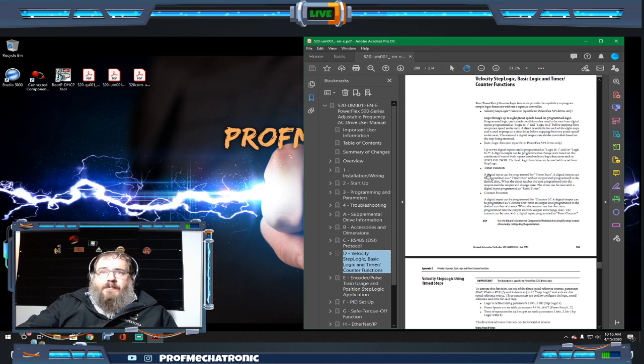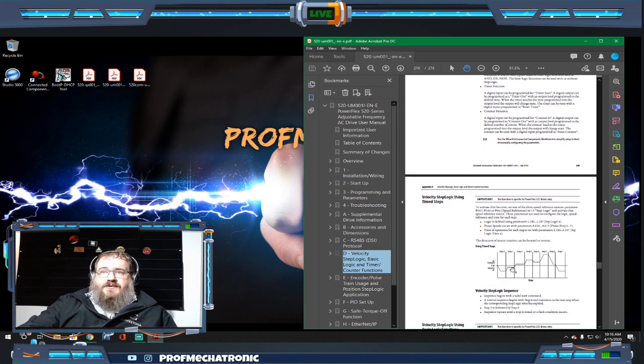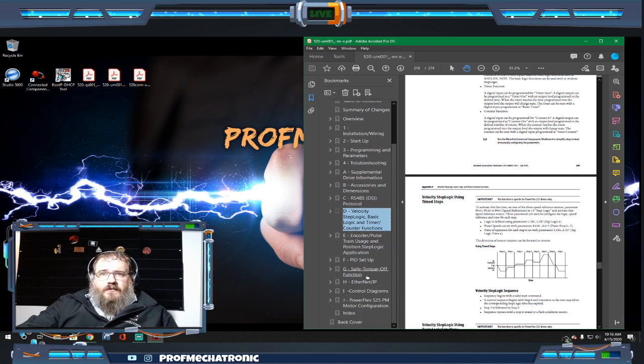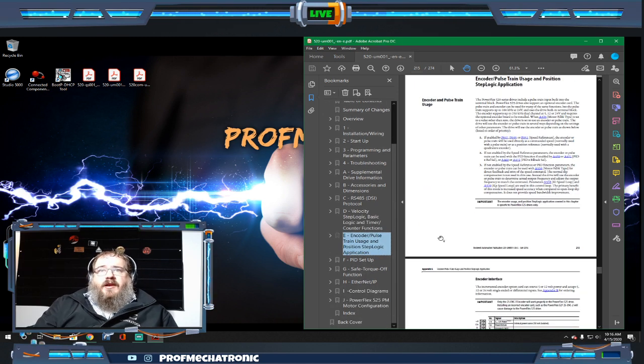You do have the capability of doing some of those steps: for step one, running in reverse, then running slower in reverse, then going forward, then moving faster. All of these steps you can see here, you have the ability to do that step logic in the VFD itself.